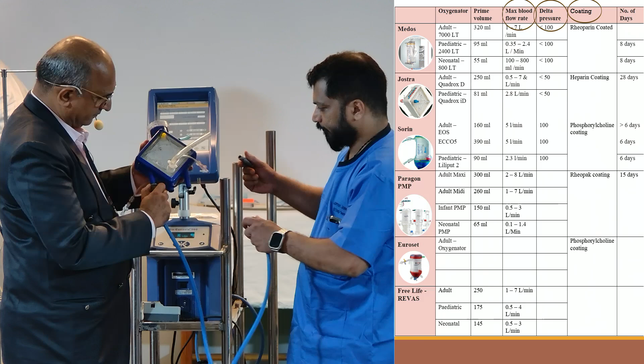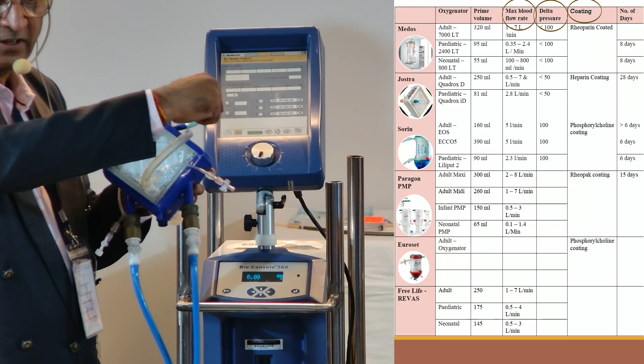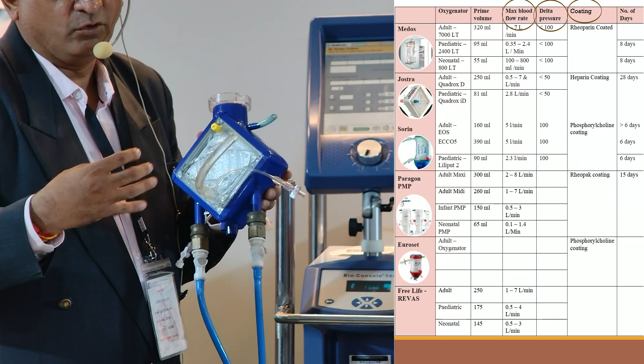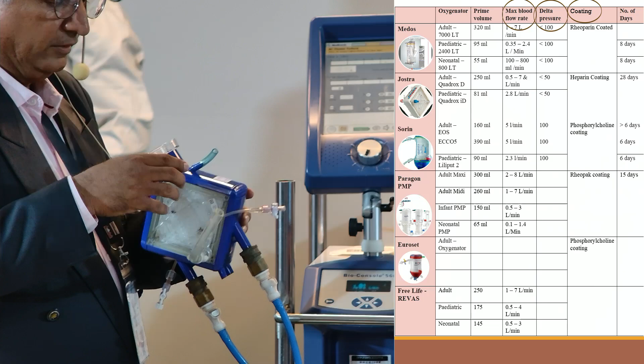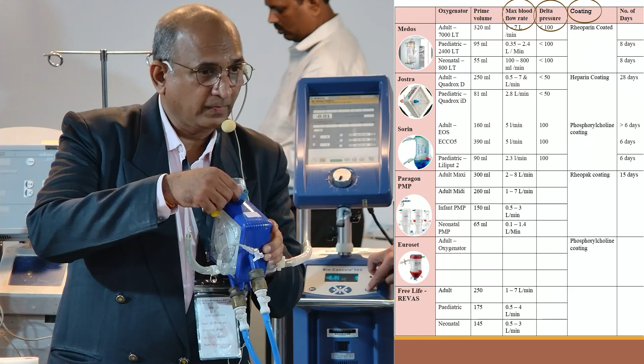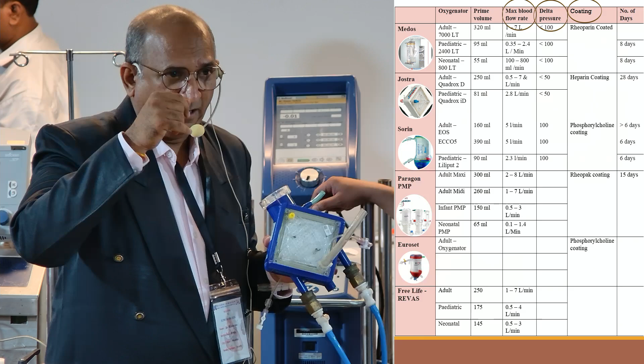So water will come from one end. It gets attached here, and water will go out from here. It moves inside and comes out. So warm water is moving around the blood, so it warms up the blood. Whatever blood cooling has occurred, it gets warmed up. Third is your oxygen line, the gas line. From here, the blood goes down. There are fibers here, very minute fibers, around 180 micron. That is the internal diameter. So the oxygen or gas flows through those fibers.